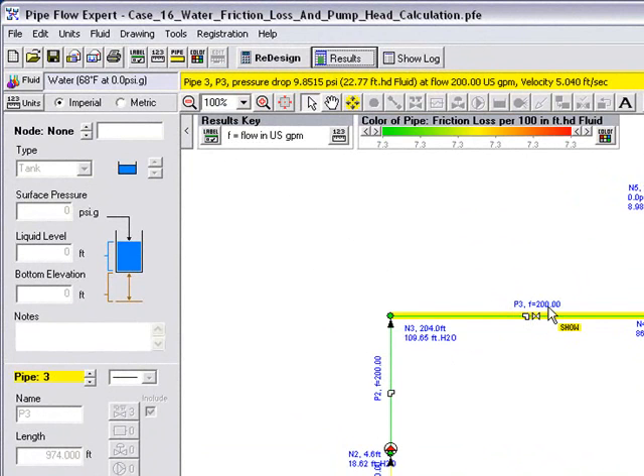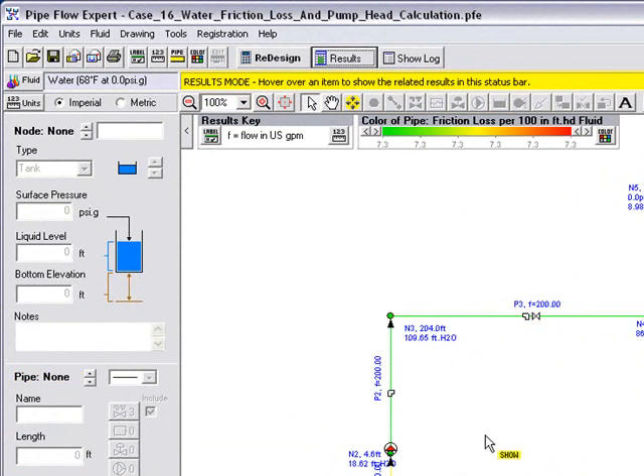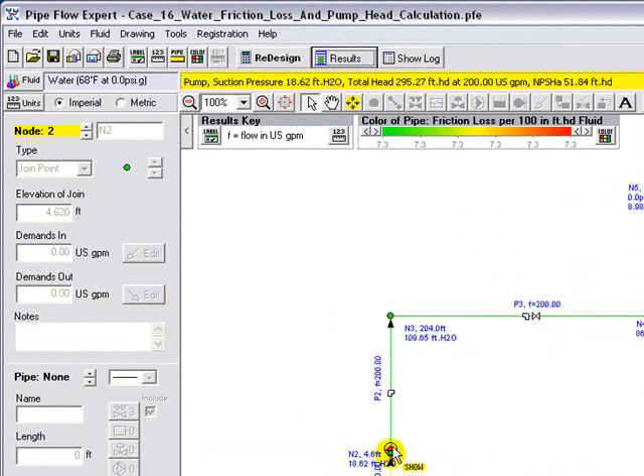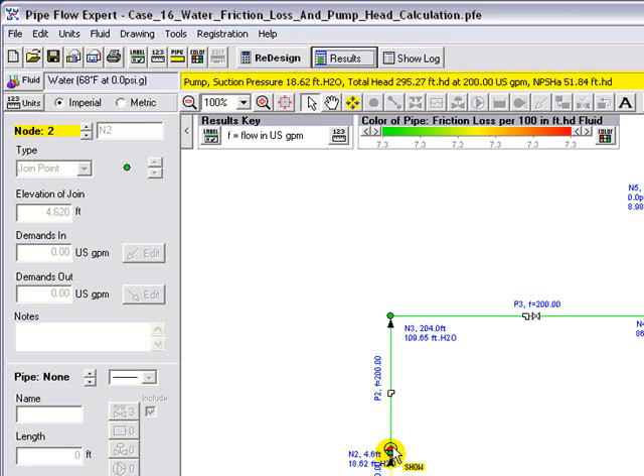And we can also hover over the pump. And we can see in the yellow status bar window at the top of the screen, the suction pressure of the pump is 18.62 feet. The total head added by the pump is 295.27 feet, produces a flow of 200 USGPM. And the NPSH available is 51.84 feet head of liquid.